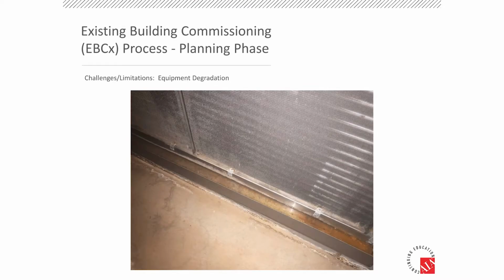Equipment degradation. Air handling units, phase 1, 2008. This is 2016 when we arrive on site and start looking at this stuff. That's 8 years of time for that equipment to naturally fall out of its optimal operation - wear and tear, especially if the operations and maintenance isn't as great as it possibly could be, which in this case I think there certainly were some things that could have been improved upon.